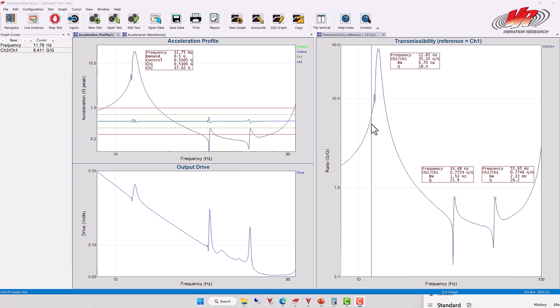How narrow the bandwidth of a resonance is has importance to the test engineer for whether or not a controller can appropriately control through that particular resonance.